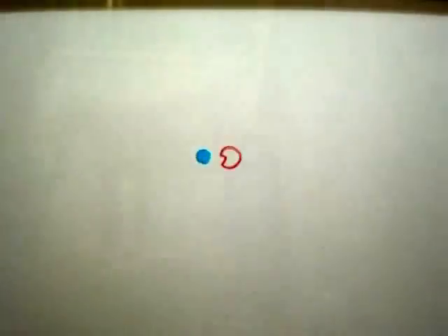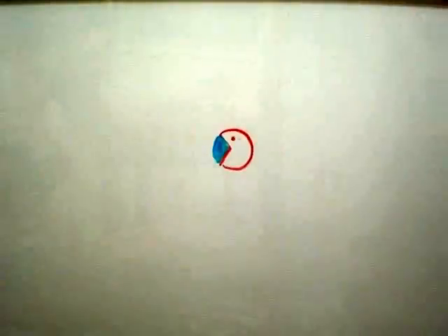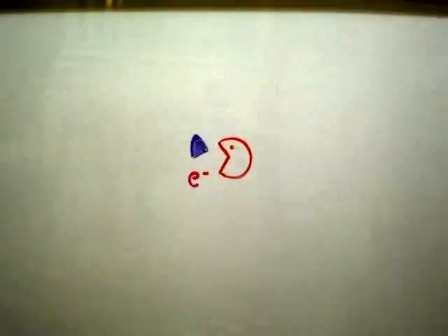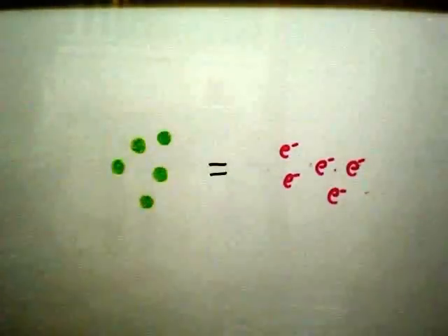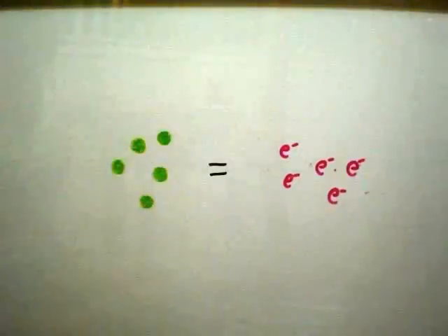Certain types of enzymatic reactions, called oxidation reactions, result in the release of one or more electrons from the molecule bound to an enzyme. Electrons are negatively charged particles, and their flow results in the phenomena commonly known as electricity. By directing the flow of electrons from the enzyme molecule complex, we can generate an electrical current whose magnitude will be directly proportional to the rate of oxidation, and therefore proportional to the concentration of the molecule of interest.